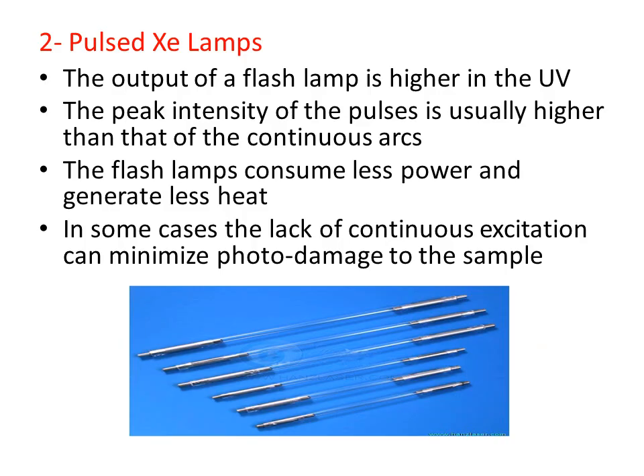Another source is the pulsed xenon lamp, whose output is produced in the form of pulses or flashes rather than continuously. The output of a flash lamp is higher in the UV region. The peak intensity of these pulses is usually higher than that of continuous arc lamps. Flash lamps consume less power and generate less heat. Another advantage is that the lack of continuous excitation can minimize photo damage to the sample.